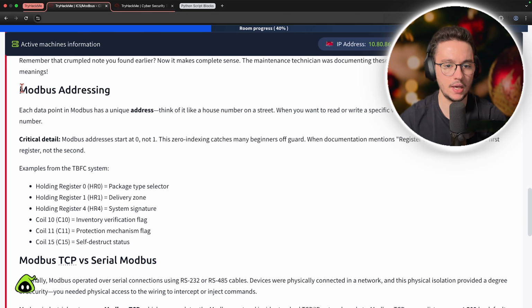So then we have some information about Modbus addressing, and one critical detail here is that Modbus addresses start at 0, not at 1. So whenever you see a register numbered 0, it literally means it's the first register.